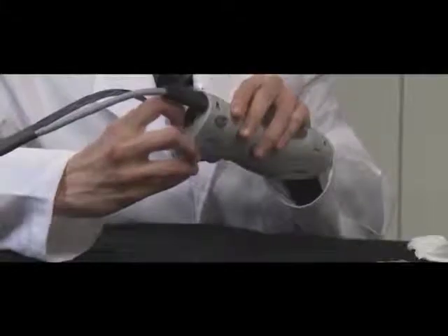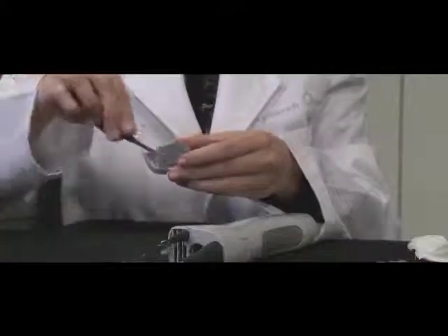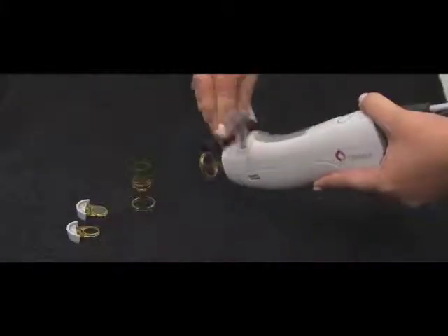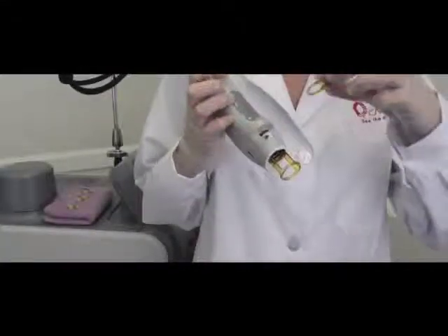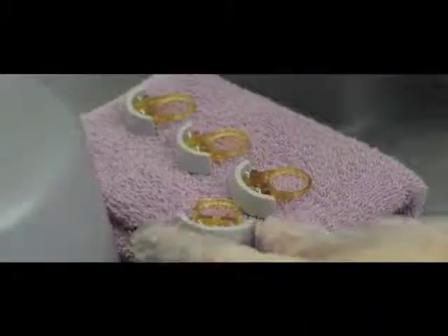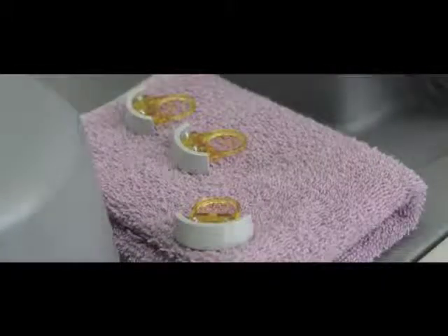The filter is removed and cleaned once per week. You may wish to do this twice per week with heavy use. The window holder is easy to remove and replace. During longer hair removal treatments, placing multiple window holders at the ready is useful for rapid changing. At the end of the treatment, all windows can be removed and cleaned at the same time. Windows should be cleaned with isopropyl alcohol and a soft cloth, gauze or lens paper. Be careful not to leave a fingerprint by touching the window with your fingers.